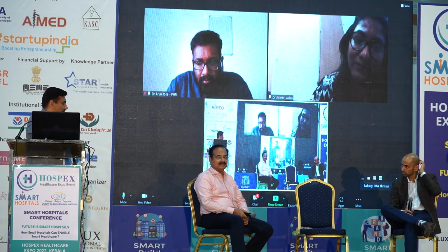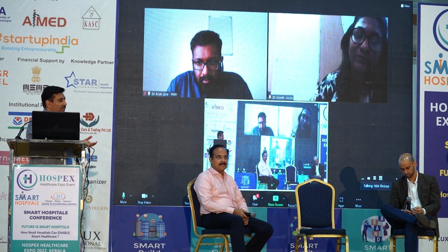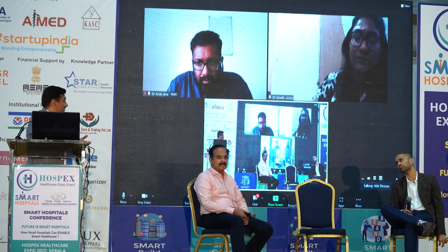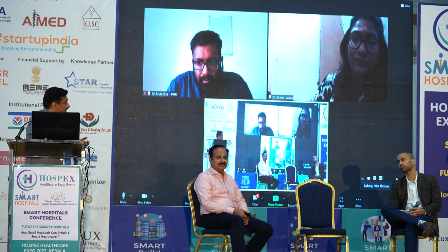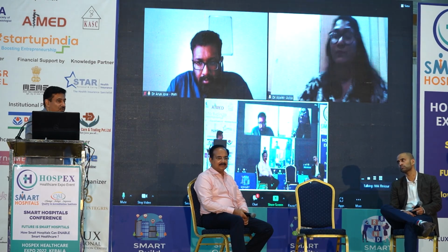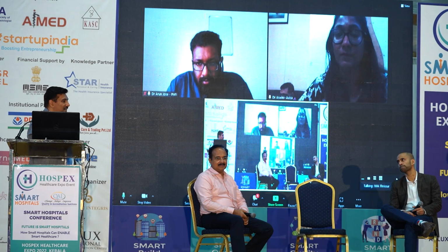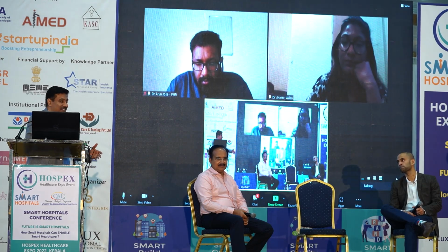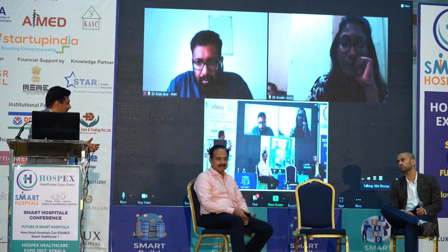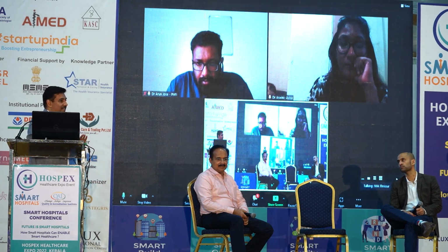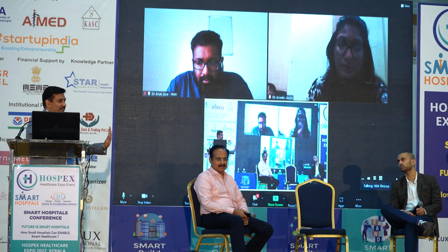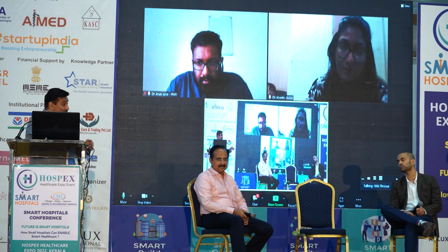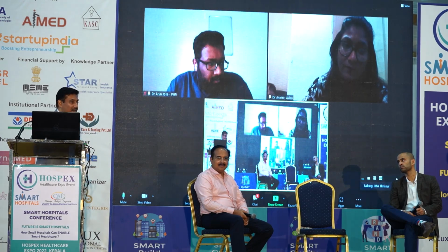In my opinion, what you guys said is that your device is compatible with the specifications, it may be FDA, CE marking, or whatever is applicable. But that equally holds good for any device used by a hospital in person, right? Still, those devices require validation, and it's not just one manufacturer. That gives a license that yes, this medical device is for this purpose, you can use it. But over a period of time, whether it continues working in the same manner and giving the same results as it should, you need to validate.